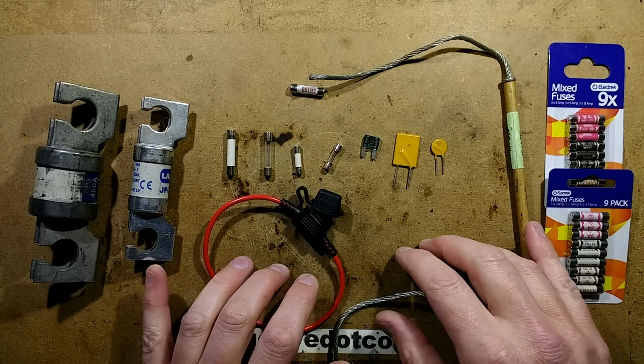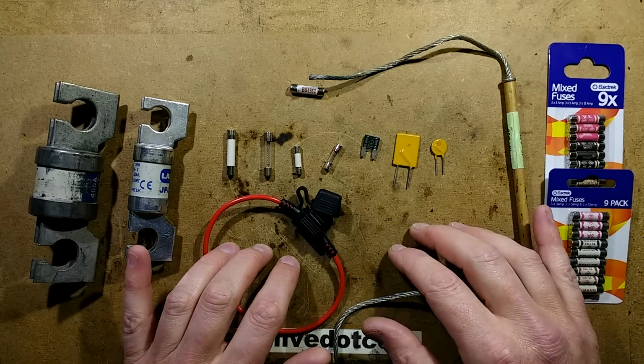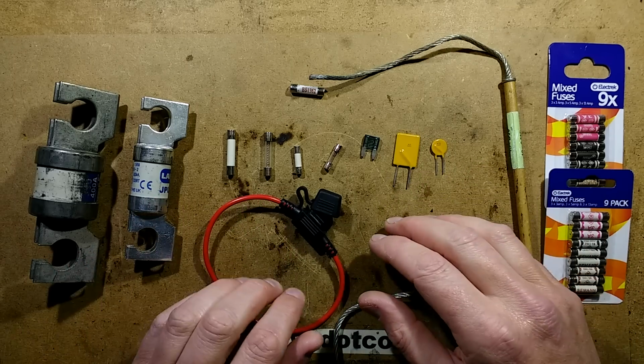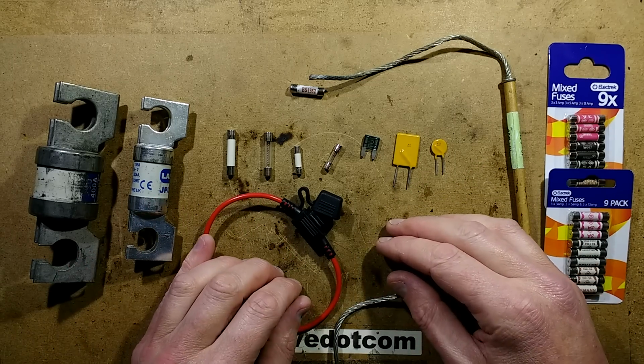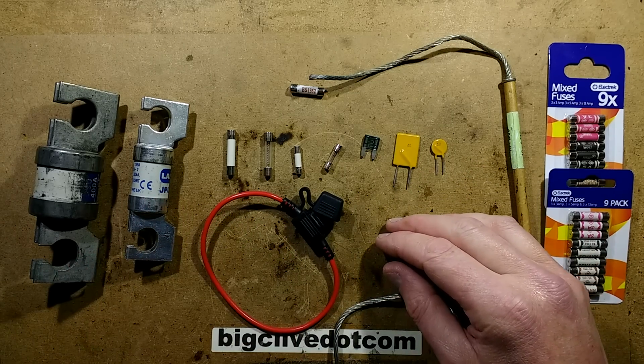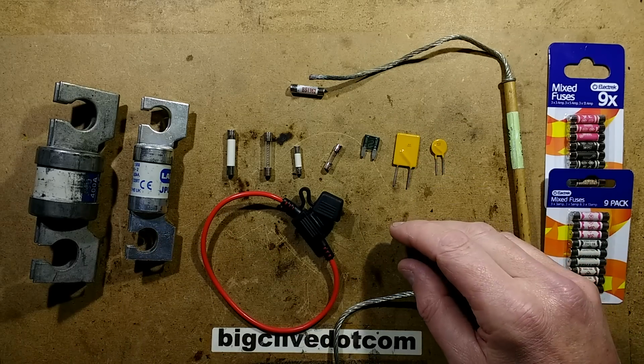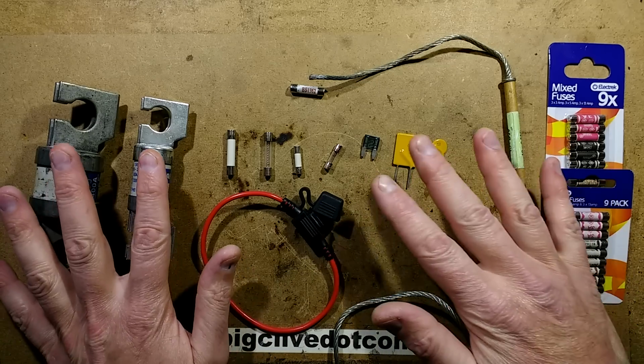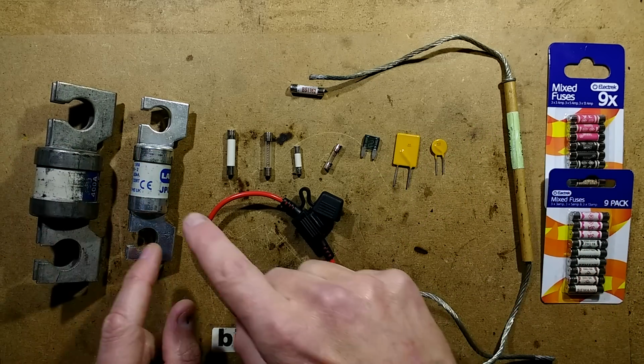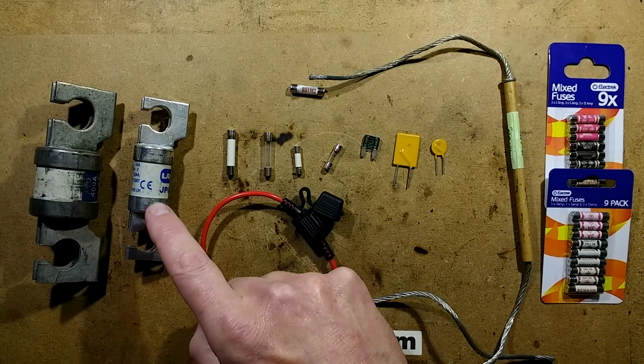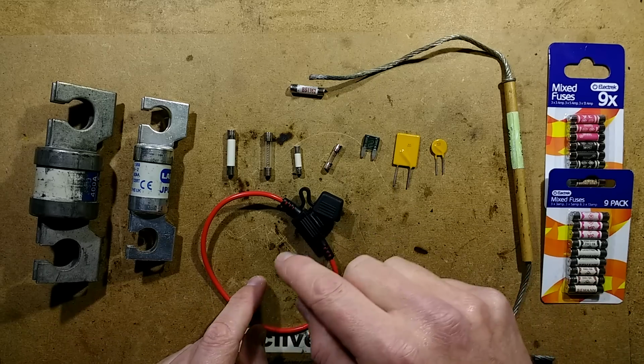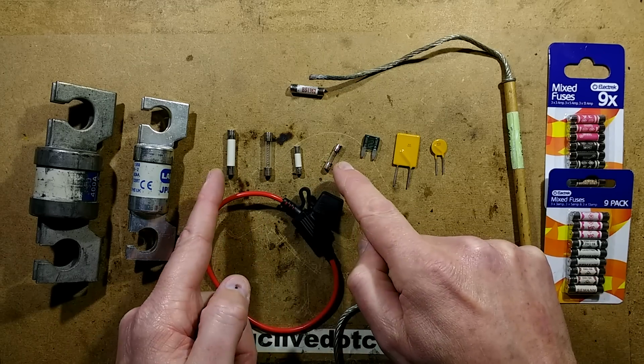Let's talk about fuses, because there's quite a wide range of fuses, quite a wide range of ratings. And apart from being the most universally abused component, it's also one of the most important for safety. And in this case, just for entertainment value, I've got some really big fuses and I've smashed one of these open, one that's been pre-blown, so I'll show you that later. A range of standard fuses that you're likely to see.